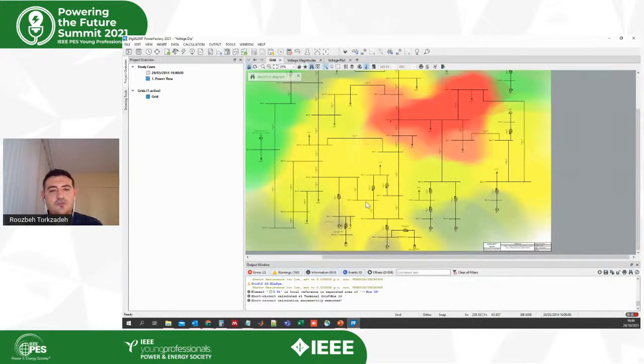This is something we need to think about for the future. If we are going toward more and more renewables, we need to also think about short circuit power changes. Maybe the point is not having a lot of renewables, but fluctuating between a lot of renewables and sometimes some synchronous machines, because we need to forecast the wind, and there will be clouding which impacts solar parks. These fluctuations in the output power of renewables would lead system operators to put synchronous generation in service. But this changing from renewable to synchronous and synchronous to renewable will cause higher fluctuations in the short circuit power, which can impact voltage dips, and also impact the protection system, and we need to think about it.